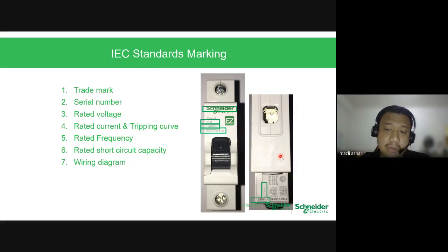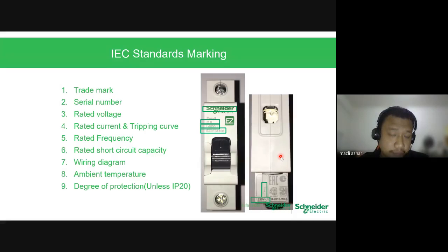Wiring diagram, you can see on the top of the product. Ambient temperature, if it's not the standard ambient temperature for Malaysia, you need to state it. Degree of protection is IP20. When I say IP20 is fingerproof, you can Google yourself what is ingress protection. Basically, IP20 being fingerproof means your finger literally can't touch the live parts when it's on. Okay, but don't try to cheat yourself. I know some of you have very small fingers, so they have a standard size for the test. I myself have tested IP20 when this thing is live, so I'm still alive and giving you a talk today.